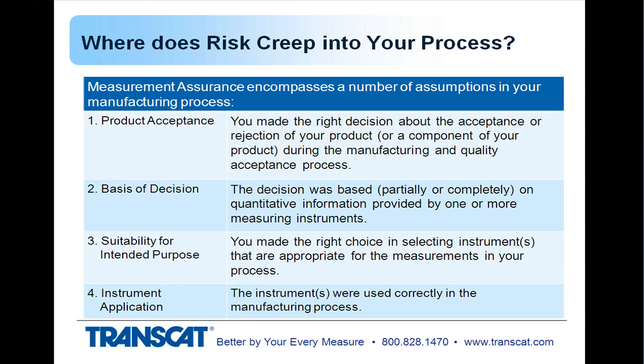The first one is product acceptance. Did you make the right decision about the acceptance or rejection of your product or a component of your product while you were in the manufacturing process and in your quality acceptance process when you were using instruments to make that decision? The basis of that decision is the instrumentation that gives you the quantitative values. Suitability for intended purpose is making sure that you've selected the right instruments for making those decisions about your product acceptance. Instrument application has to do with using the instrument correctly. You may have selected the right instrument, but are the things that you're doing causing errors in the measurements?